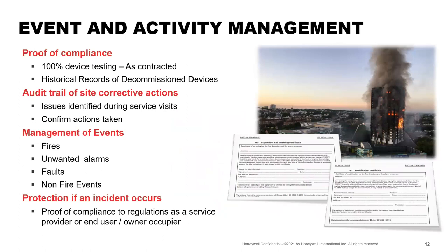So we're looking at the following things. 100% device testing has been completed. This ensures that all initiating devices have been fully tested or are in fully working order. That basically means any detector or any input that it's working properly and that it kicks off when it needs to and it does what it needs to do. We're making sure that the devices have been disconnected within the service period and that records have been investigated. This comes under the decommissioned tab.